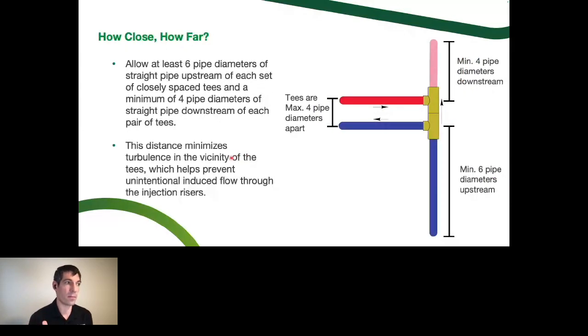Here is the "but" portion of that answer, and this is really critical. If we say closely spaced tees, the book answer is no more than 4 pipe diameters apart. In a lot of boiler manuals for years, it would say things like maximum of 12 inches. That's a good answer if you've got 3-inch pipe, but a bad answer if you've got 1-inch pipe. We don't want 1-inch pipe to be 12 inches apart. That's not closely spaced anymore. There's going to be more of a pressure drop here, and the path of least resistance may be, instead of separating that gear where the GPM come back here, if it's in excess of what we need on the system side, some of that peels off and starts to push the circulators downstream out into the system side. We've broken that scenario, and we've started to bring the gears back into conflict a little bit.